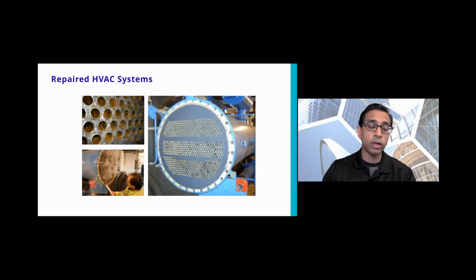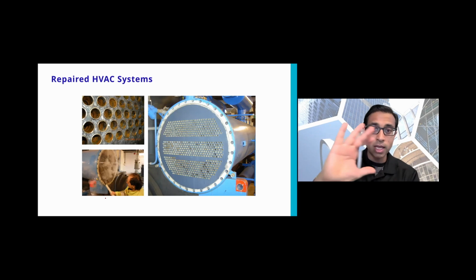So what can be done? These systems can be repaired. You can see it right here—it's the same exchanger face as in the last picture. In this case, the exchanger face is actually being steamed out, cleaned off. Once it's cleaned, remember I talked earlier about the fillers—in this case we're going to use the metal filler to rebuild that face.